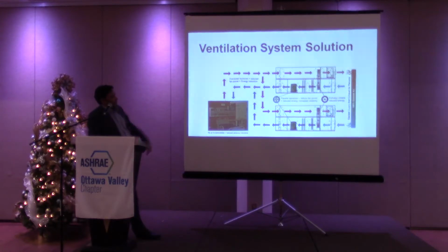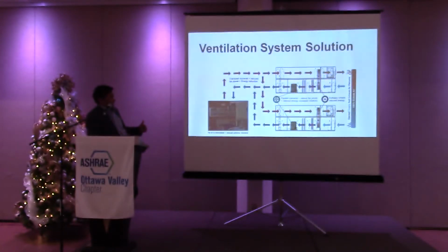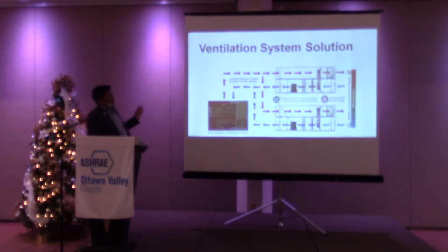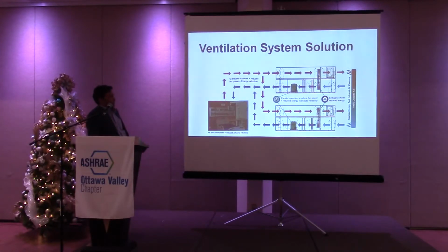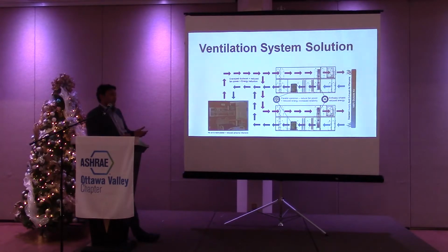This slide just talks about the 100% outside air that we're required to provide to the building. So we oversize, we're bringing the outside air right through into the spaces, exhausting all the air from the washrooms, returning to the enthalpy recovery wheels. So in this building, we focused on recovering heat through enthalpy recovery wheels through bathroom exhaust.